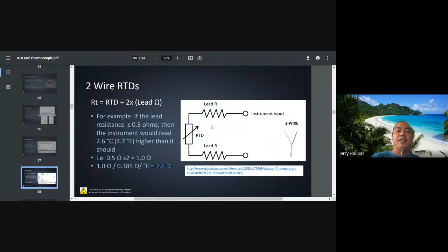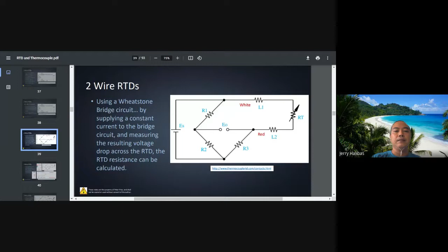So you need to compensate by adding a conditioning circuit. You'll find this conditioning circuit in your temperature controller or even a PLC, as an additional module you need to attach to compensate, so that the effect of L1 or L2 resistance will be canceled out. Okay, that's for the 2-wire RTD. That's how the conditioning circuit compensates.